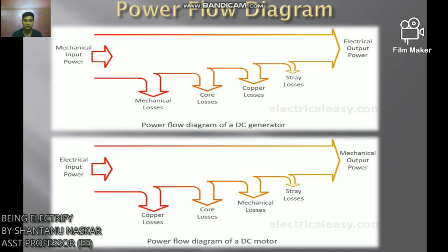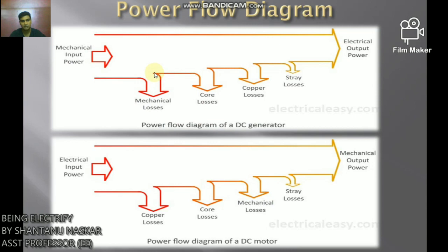The power flow diagram is the most convenient method to understand losses in a DC generator or DC motor. The diagram visualizes the amount of power lost in various types of losses and the amount actually converted to output. For a DC generator: mechanical power is the input, then mechanical losses occur, then core losses, then copper losses, then stray losses, and the output is electrical power. For a DC motor: electrical power is the input, then copper loss, core loss, mechanical loss, stray loss occur, and the output is mechanical power.